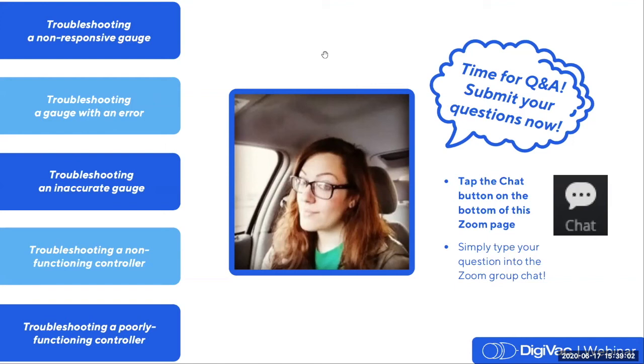We have another message from John. John, this is an excellent point, one that we should have outlined before. Can you go over the difference between the Agilent 531 sensor and the 536? Great question. The 531 and the 536 are both fully welded stainless steel. The only difference between them is that the 536 sensor has a small shield, which we call a baffle, that very partially obscures the thermocouple wires inside the sensor. In the 531, you may peer in and see the little X made by the filaments inside, but the 536 has a baffle that partially blocks those off.